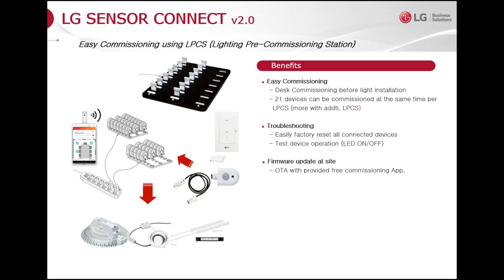So what we've come up with is an LPCS, a lighting pre-commissioning station. It's a station with 21 ports for a dongle or sensor. You can connect 21 sensors, 21 dongles, or any combination. It powers them on, and it's got an LED for every connection, essentially a little light, so it's like having 21 fixtures on your desk. You can do this from your office, all it takes is a USB cable to power it. As long as the dongle or sensor has power and a little LED indicator, you can commission it with the app before installation.